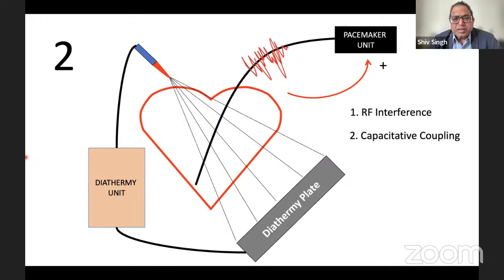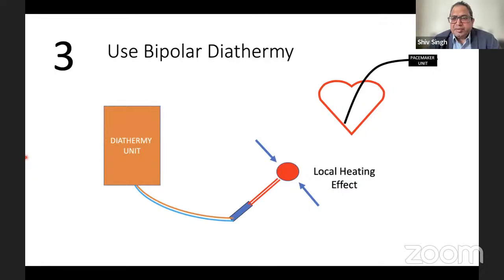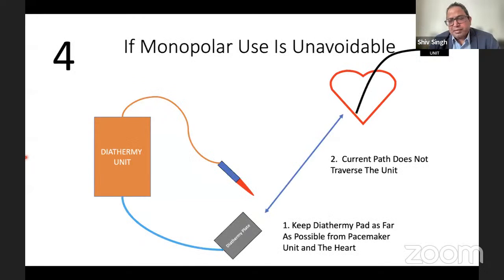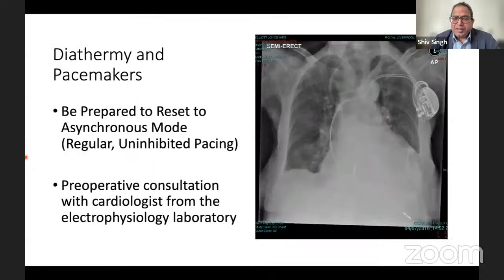The best thing to use when you have pacemakers is bipolar diathermy. The current path should not traverse anywhere between the pacing unit, which is implanted below the clavicle, and the wires, so there should be no current flowing in that direction. You need to keep the diathermy pad as far as possible from the pacemaker unit and the heart. Even the diathermy unit should be kept as far away from the patient as possible. If the pacemaker unit is on the left side, move the diathermy plate to the right side near the foot end. That will reduce the interference. And if anything goes wrong, be prepared to reset to asynchronous mode. That requires having a magnet over the pacemaker, which changes it to asynchronous mode. You take it off and it resets back to normal.